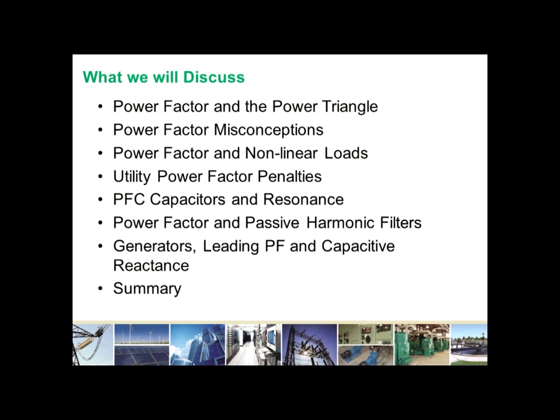Today we'll be discussing power factor and the power triangle, the 6 misconceptions of power factor, nonlinear loads and the harmonics they generate and their impact on power factor, utility power factor penalties, power factor correction capacitors and the potential for resonance with the power system, passive harmonic filters and their relationship to power factor at various load levels, and the effect of leading power factor and capacitive reactance on generators.